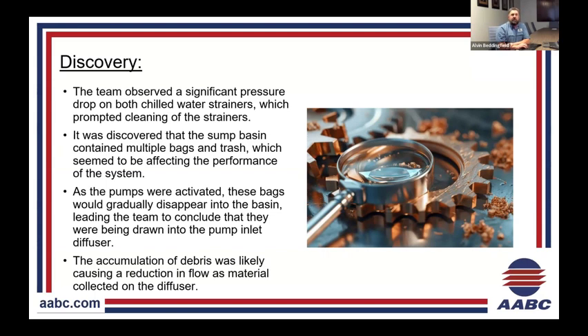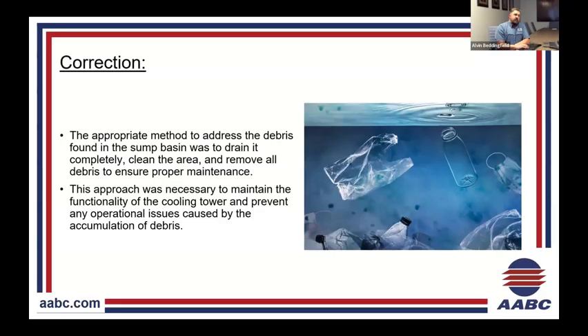So what we concluded back to the engineer was, hey, we believe the trash bags are being drawn into the inlet pump diffuser. And once it ran for 10 to 15 minutes, those bags would just cling to that basket and restrict all the flow. That's one of the reasons why I feel we were getting inconsistent flow. One time it would be a little bit less, one time a little bit more, and that was just because of how much trash there was each time, once the pumps cycled off and it floated up, and how fast it would get pulled back down to the inlet pump diffuser.